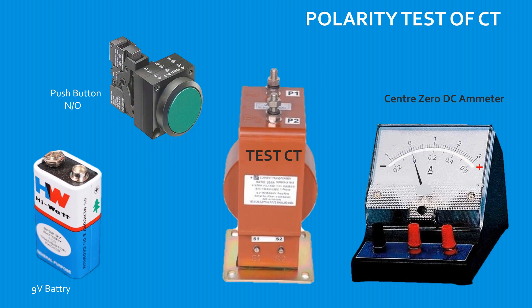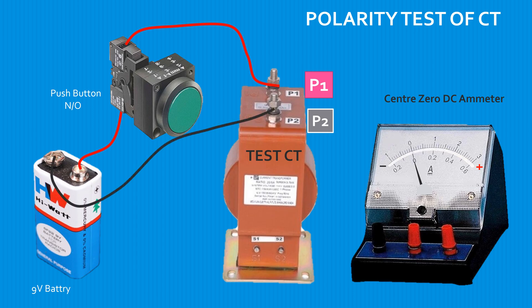Identify and mark permanently the P1 and P2 terminals on the CT to be tested for polarity. Connect the positive terminal of the 9-volt cell to the P1 terminal of the test CT through a test push button. Connect the negative terminal of the 9-volt cell to the P2 terminal of the test CT directly.